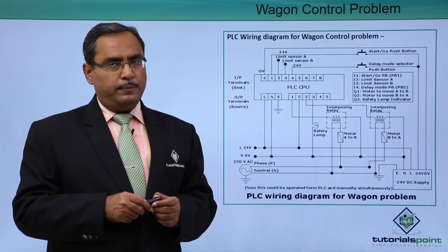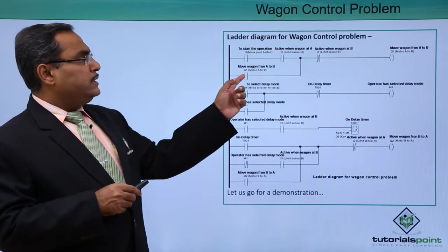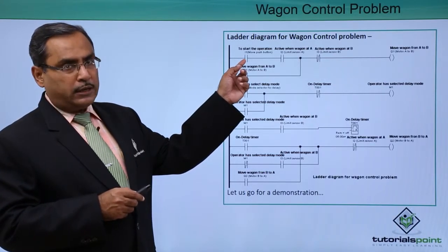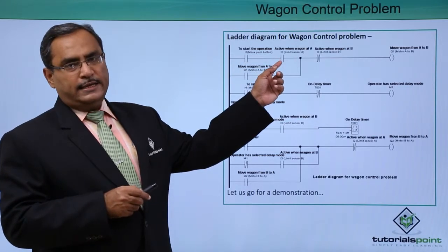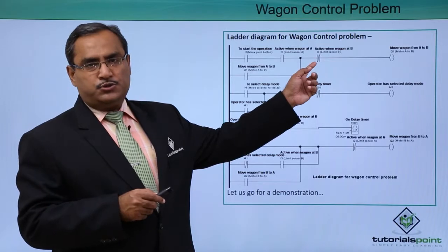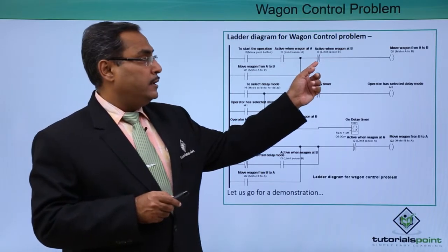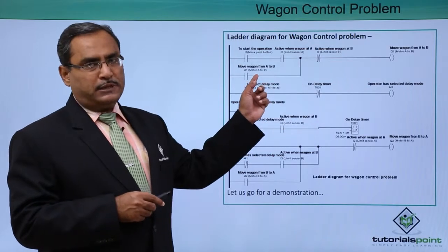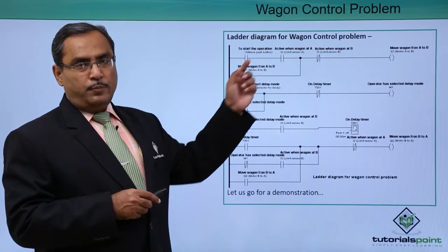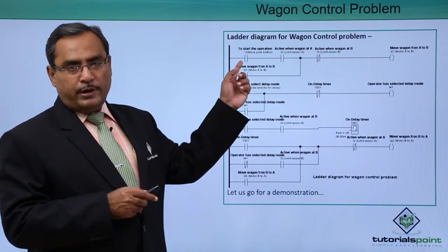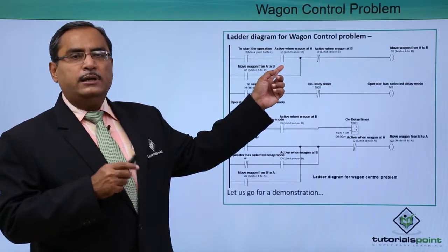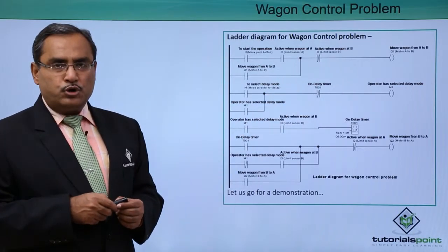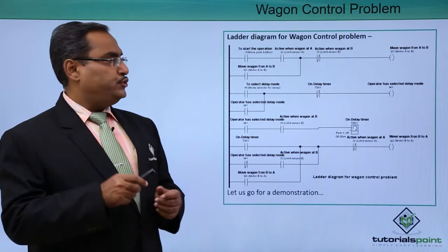This is the ladder diagram for the wagon control problem. When the start push button is pressed and the wagon is at sensor A, until it reaches sensor B (limit B), the motor carrying the wagon from A to B will be on. A parallel latch path bypasses the push button contact, because when the push button is released the wagon is between stations and limit sensor A can no longer sense it. So the wagon remains in motion until it reaches station B.